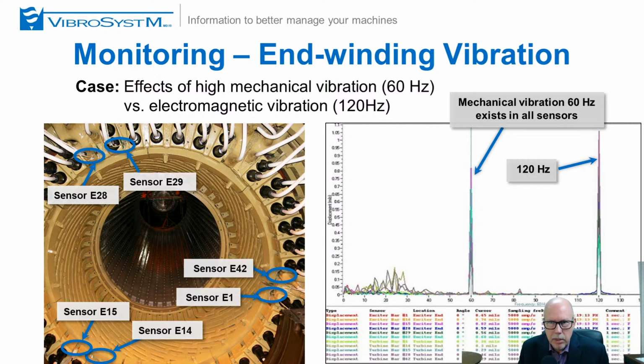And in reality, when we called the customer, we assumed that they were having high shaft vibration issues. And they were surprised to hear this from us, because they were. And they asked us how we could tell that they had shaft issues. And we said, well, we can see it on the end windings. The 60 hertz is transferred from the shaft to the bearing down to the foundation, back to the housing, back to the frame and core, and eventually at the end winding. So this is a case where very high shaft vibration was actually showing up on the end windings.